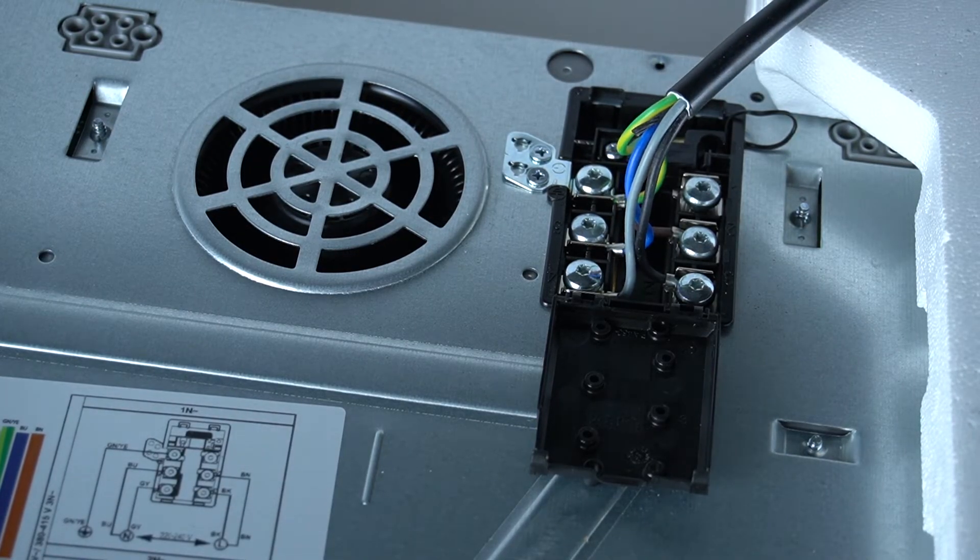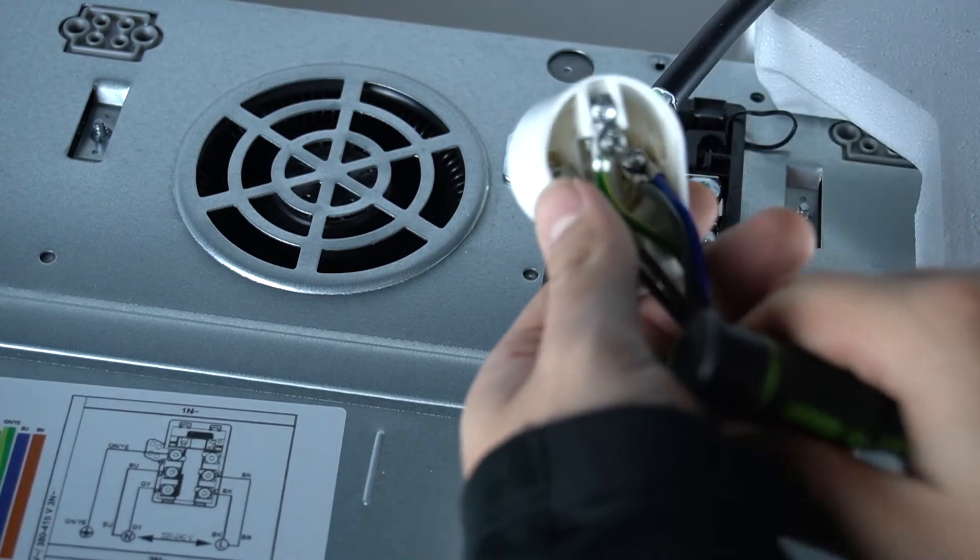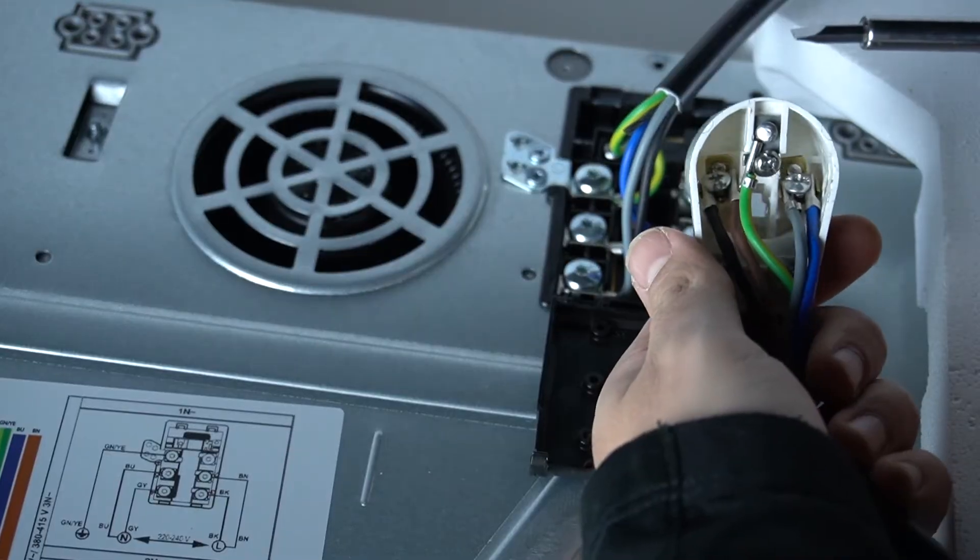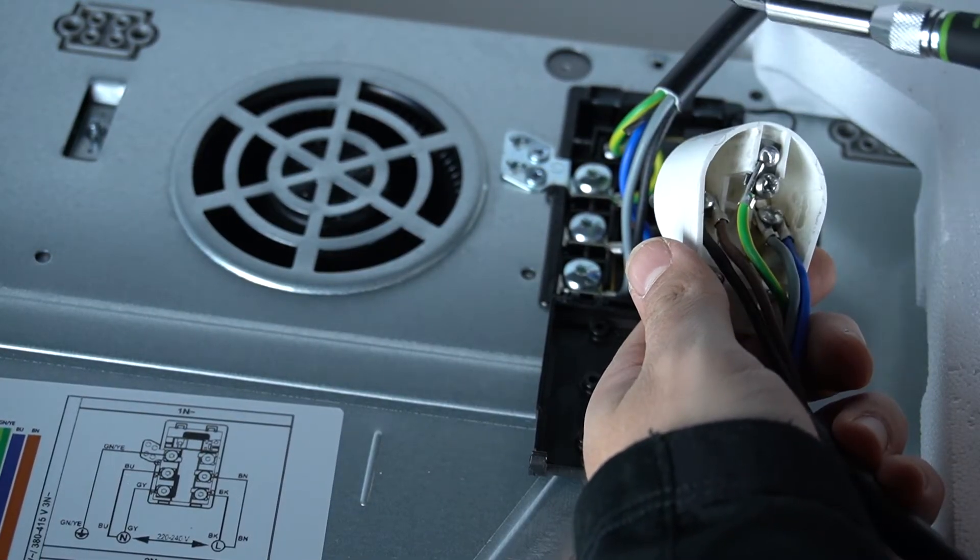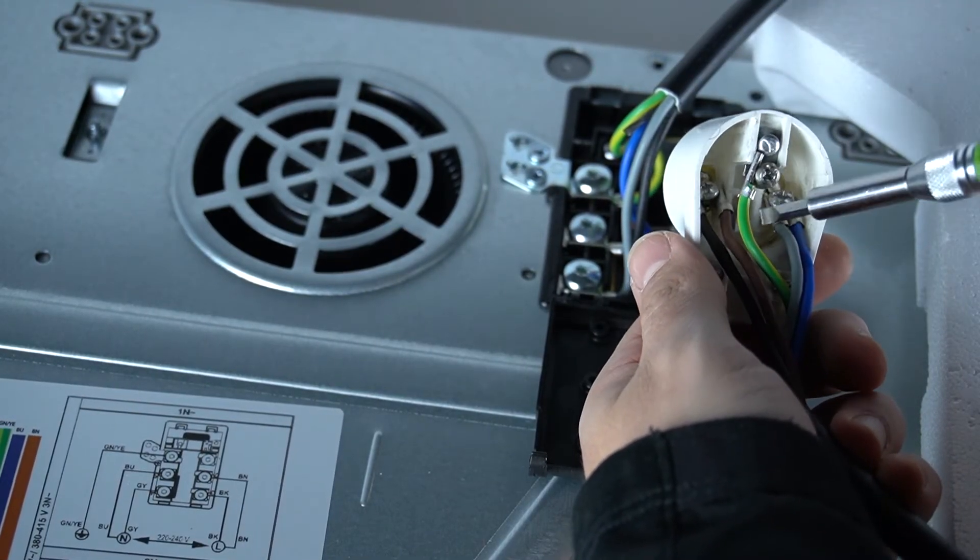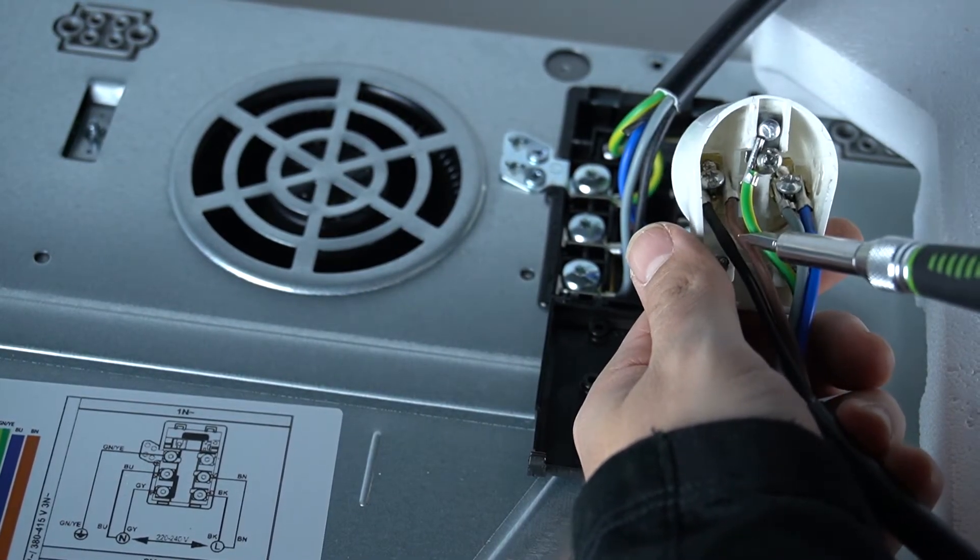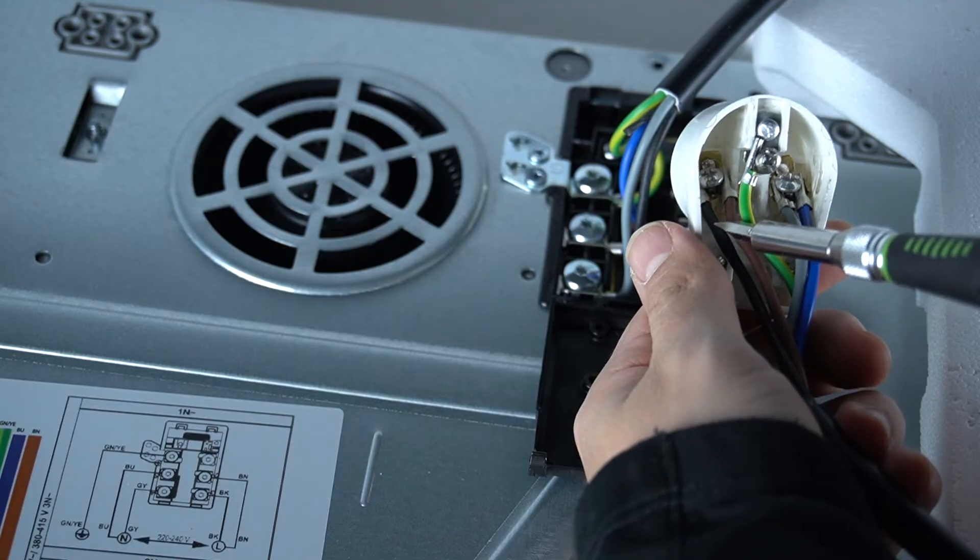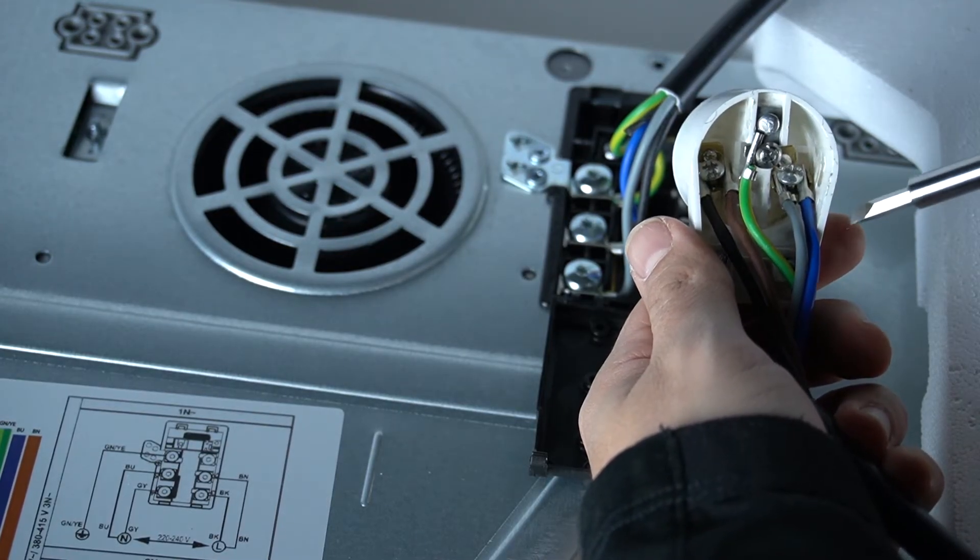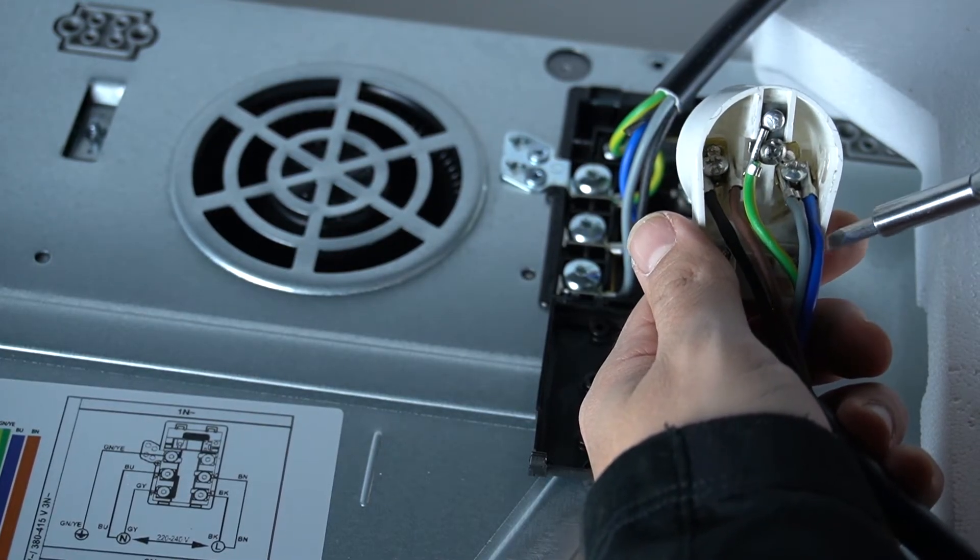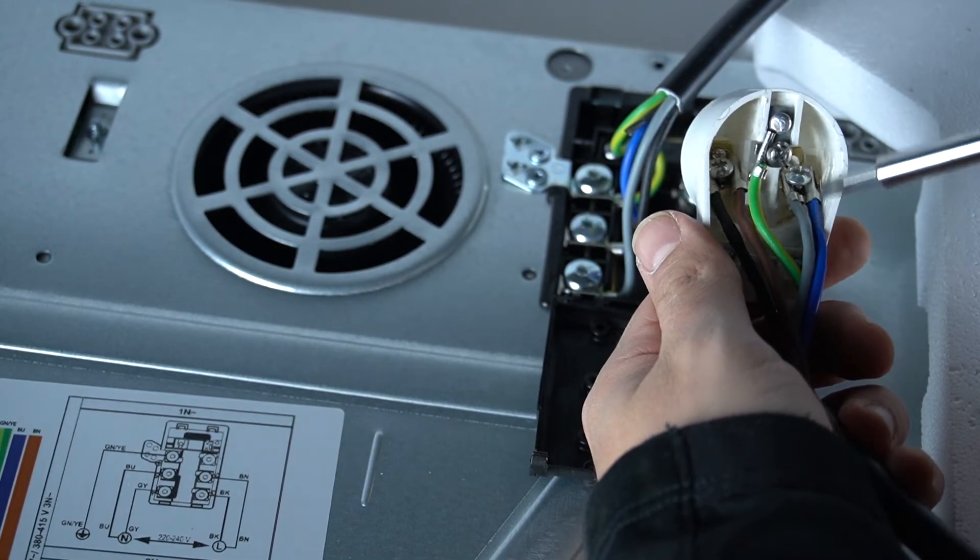Now let's go to the plug. There we have the plug. In the normal single phase installation, we have to wire screw together the brown and the black one on the left side and on the right side the blue and the grey one.